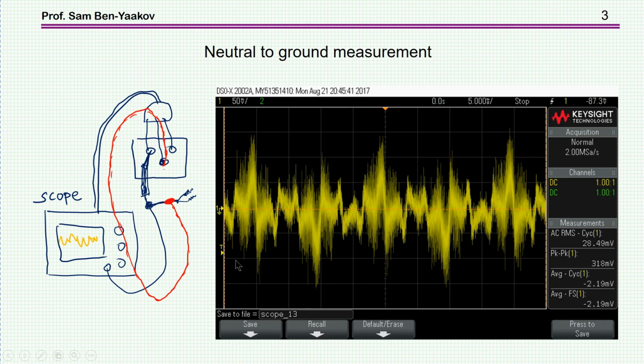The first measurement I've done is to look at the neutral. We have an oscilloscope here, and this is the 3-pronged socket with the plug of the oscilloscope. Here's the probe, put to the neutral side. This side, the ground side, is open, but internally it's connected through here to the local ground. So the measurement is in fact between the neutral and ground.